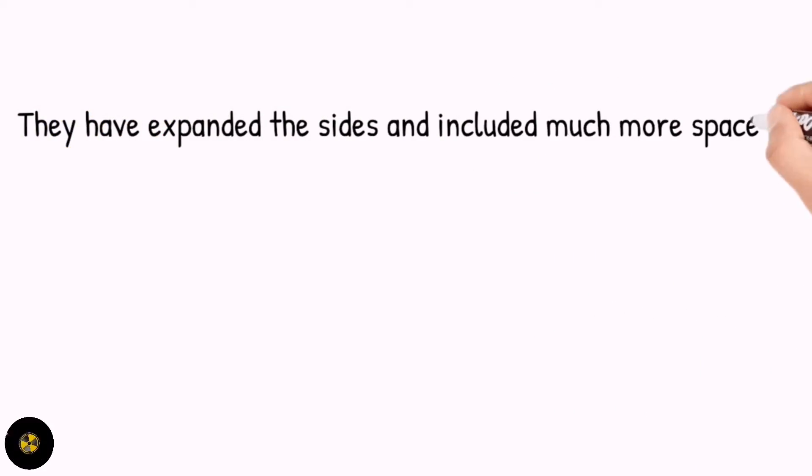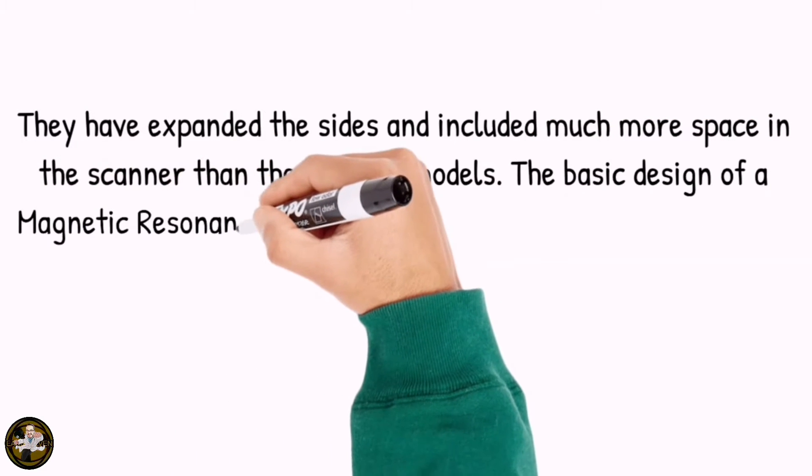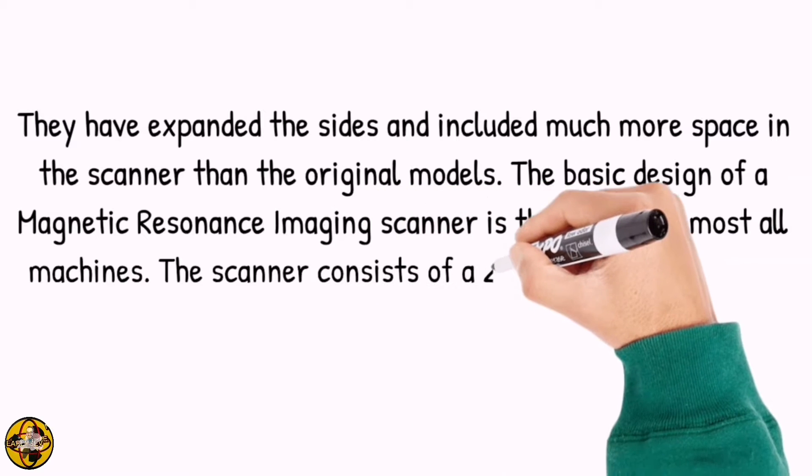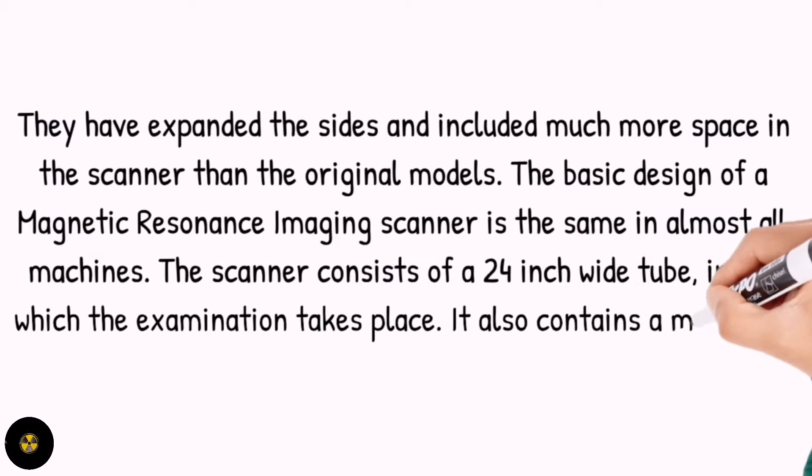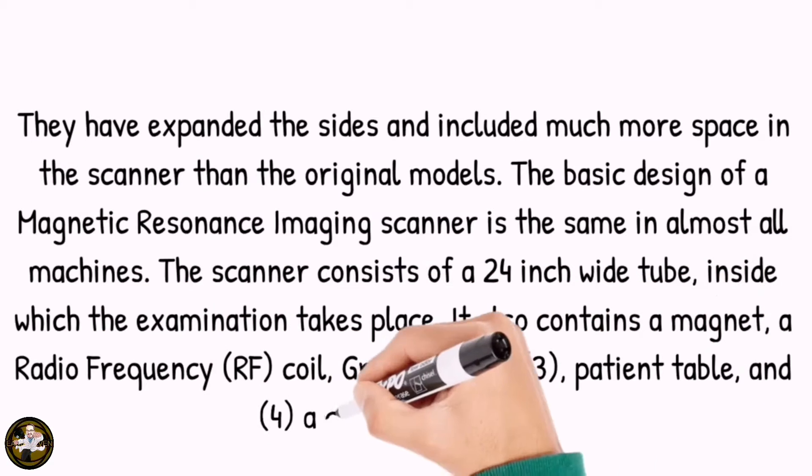They have expanded the sides and included much more space in the scanner than the original models. The basic design of a magnetic resonance imaging scanner is the same in almost all machines. The scanner consists of a 24-inch wide tube where the examination takes place. It also contains a magnet, a radio frequency coil, gradient coils, patient table, and computer system.